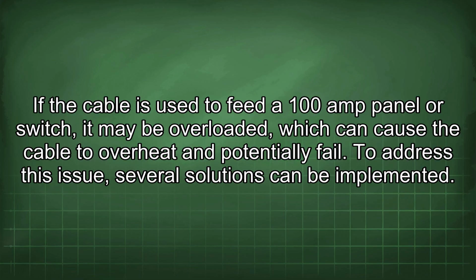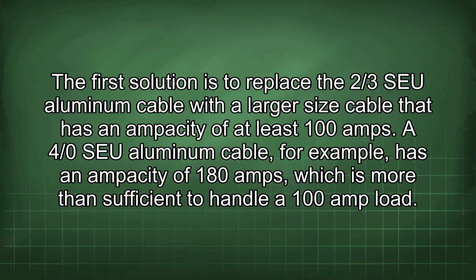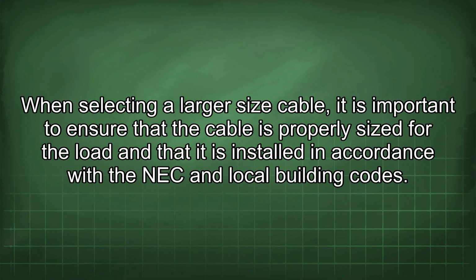To address this issue, several solutions can be implemented. The first solution is to replace the 2/3 SEU aluminum cable with a larger size cable that has an ampacity of at least 100 amps. A 4/0 SEU aluminum cable, for example, has an ampacity of 180 amps, which is more than sufficient to handle a 100 amp load. When selecting a larger size cable, it is important to ensure that the cable is properly sized for the load and that it is installed in accordance with the NEC and local building codes.